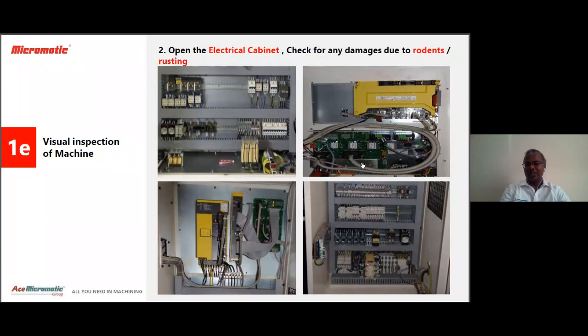There also is sufficient place where a rat can sit and cause damage. You should check this area properly for any damage or rusting. If there is damage, please change the cable or try to solder it wherever a cut has happened. We recommend it is better to change the cable to avoid future problems.